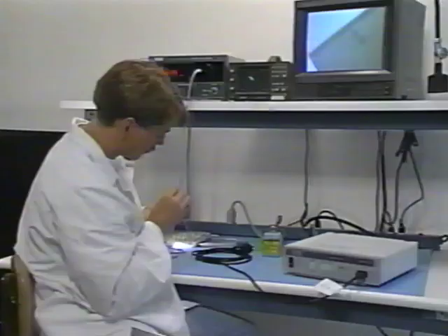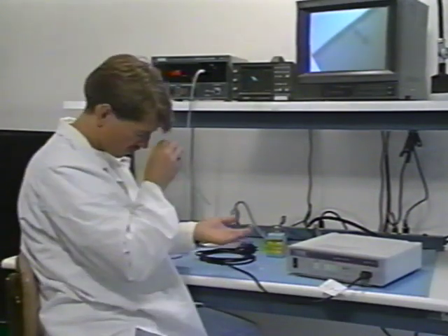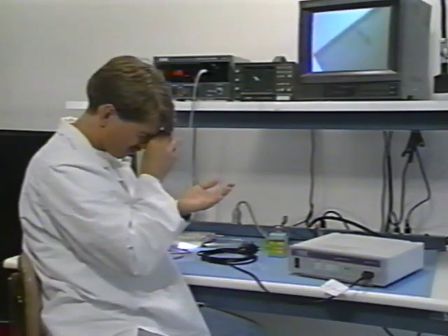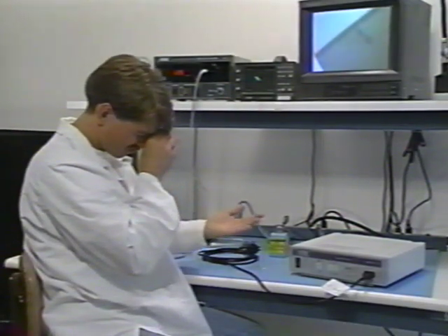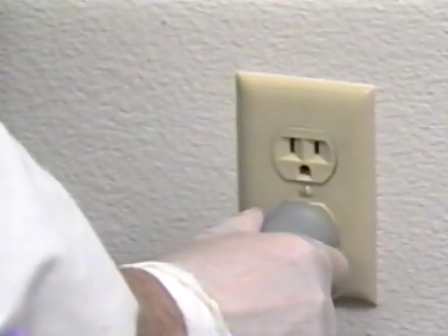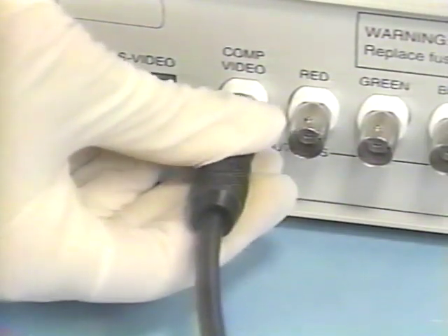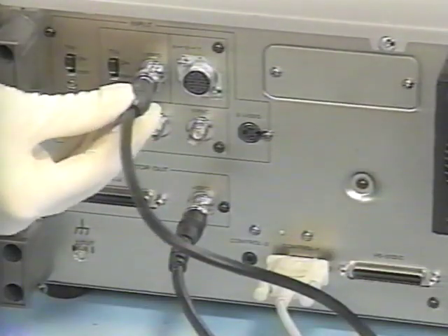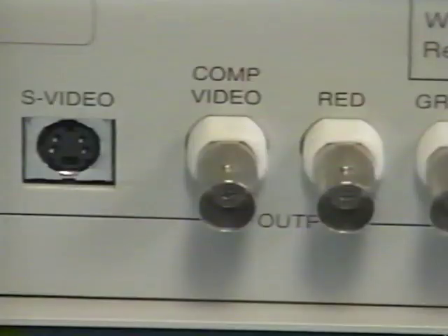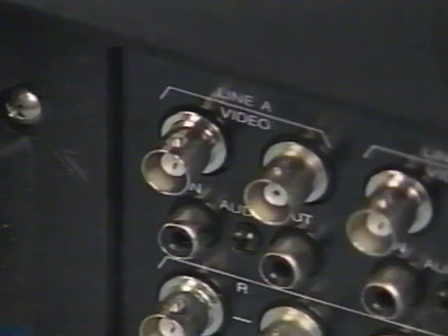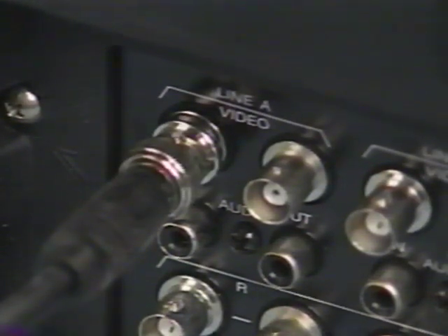Although the camera is part of a bigger chain, it is often considered the culprit when things go wrong. Usually, however, the camera is not at fault, and a simple adjustment is all that's needed somewhere in the system. If the OR calls you and says, "The camera is not working, there's no picture on the monitor," you will need to draw on all the information presented in this video and check piece by piece through the system. Check connections and power cords, including the camera, monitor, and any additional documentation devices being used, such as VCRs or printers. Double-check that the cables are run from video out to video in throughout the chain of equipment.